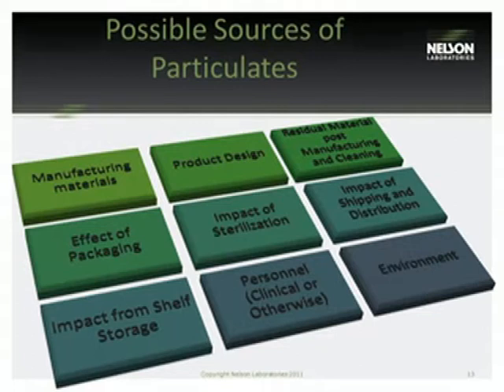Typically, it's good to include those in the final product before testing to see if maybe that's a common source of particulate matter. We've participated in quite a few investigations in which we've tried to trace down, working with our client, the source of particulate matter. And we've found that all of these can have an impact. So it's important to look at all aspects of the manufacturing process, from the raw materials all the way to the packaging and handling at the end, to determine which parts of that process may be contributing particulate matter to the device.